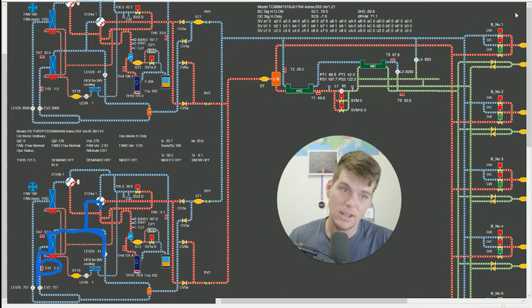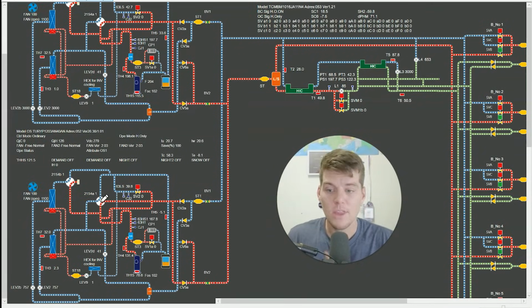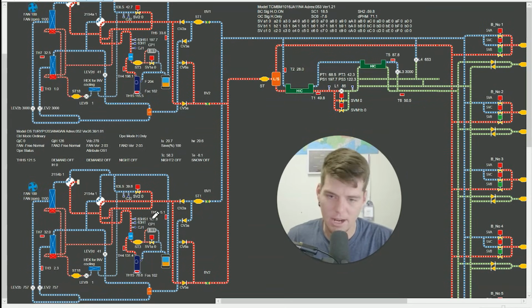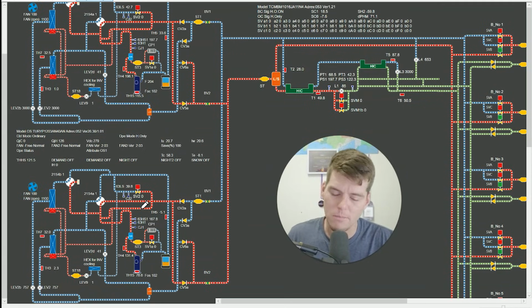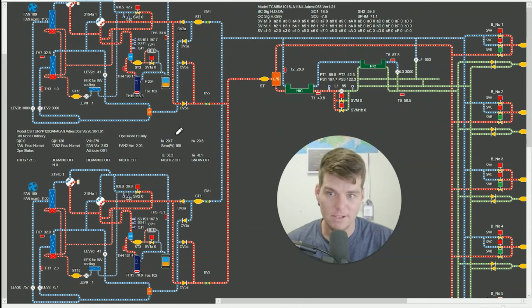Well, this is the reason that I have a complaint. The complaint is not enough temperature sensors in the system to troubleshoot this. However, understanding how refrigerant operates and that the submodule being flooded and flooding, this is where I'm going to spend most of my time investigating the problem. More so, well, we know that if this one floods here and goes this way, then I'm going to have what? I'm going to have a leaving coil temperature close to TC, right? Because it's creating subcooled liquid when you send hot gas to an outdoor heat exchanger in 32-degree ambience. However, what happens when this four-way valve fails?